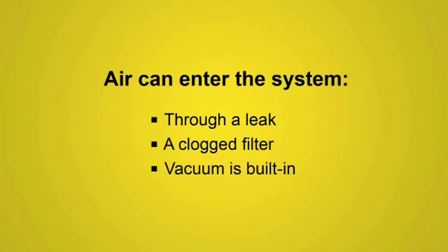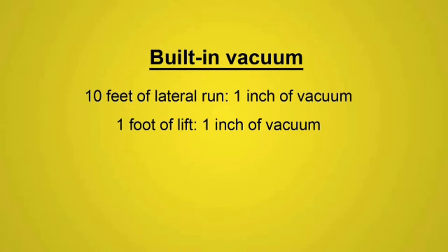Another way is when the system is built. Vacuum is inherently built into the system. For every ten feet of lateral run, you have an inch of vacuum. For every foot of lift, you have an inch of vacuum. For every fitting or device, you have an inch of vacuum. All this could add up to five or six inches of vacuum easily.